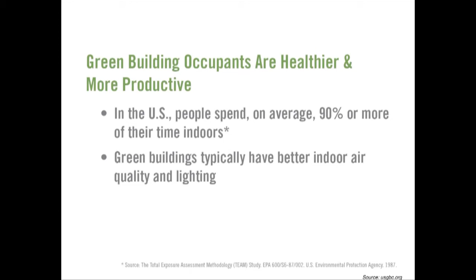Ventilation is just a huge component on any school or any building with people in it, and it's one of the more difficult things to condition in a building as well. Because if you don't condition raw outside air properly, especially in the Rio Grande Valley, you're going to be bringing a lot of humidity into the space, which is going to create mold and other issues. So it's very important that the ventilation is brought into the building properly. Now, if you do not include energy recovery, you're looking at about 36% of your air conditioning load. And the energy cost expenditure is about 27 cents per square foot in doing so.